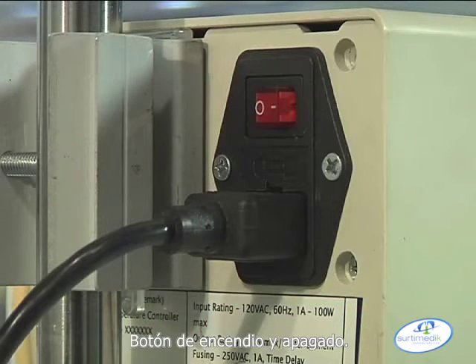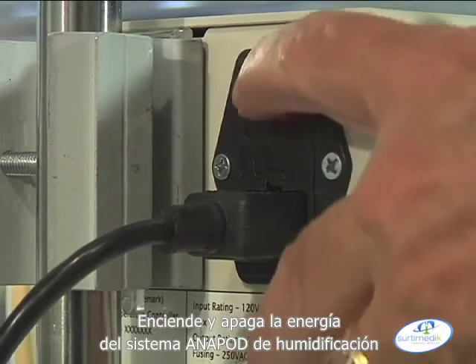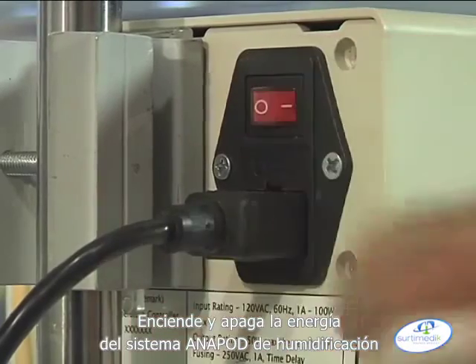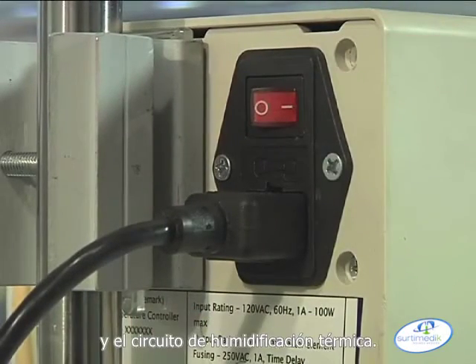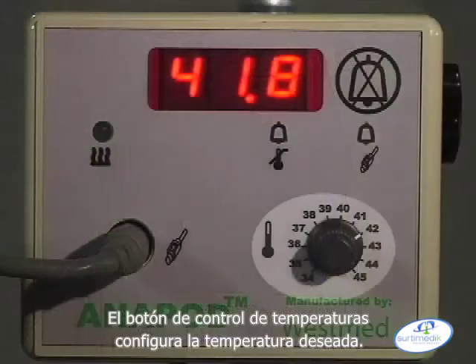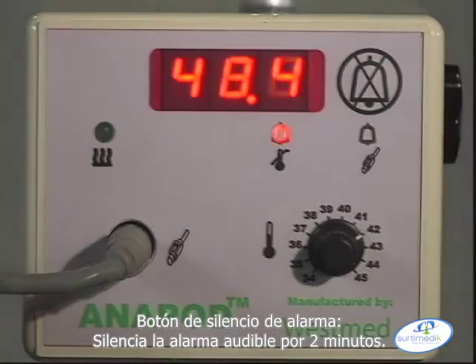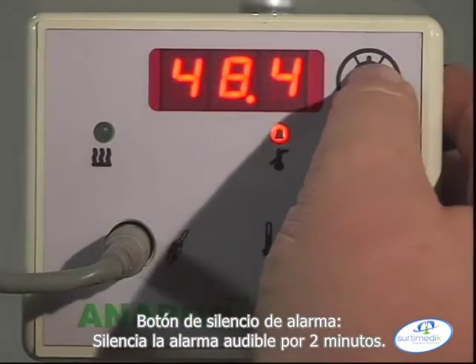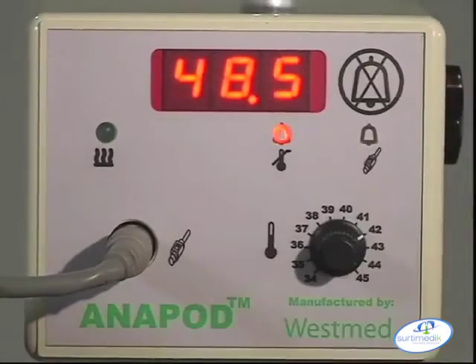Controls. On-off switch. Turns the power on and off for both the Anapod humidification system and heated wick circuit. Temperature control knob sets the desired temperature. Alarm silence button silences the audible alarm for 2 minutes.